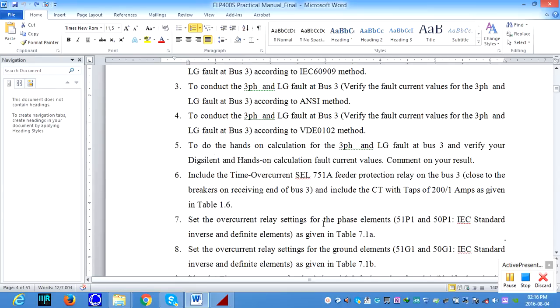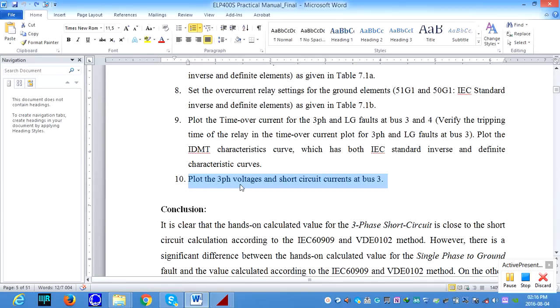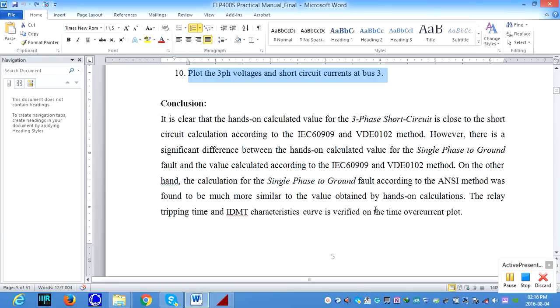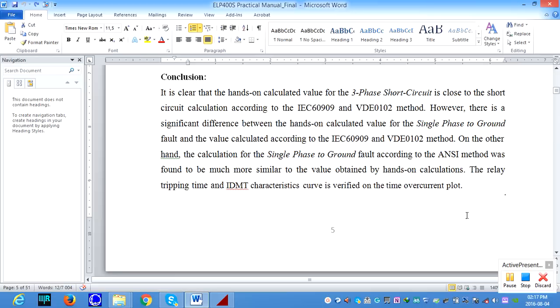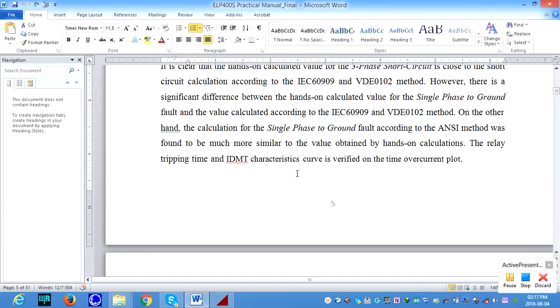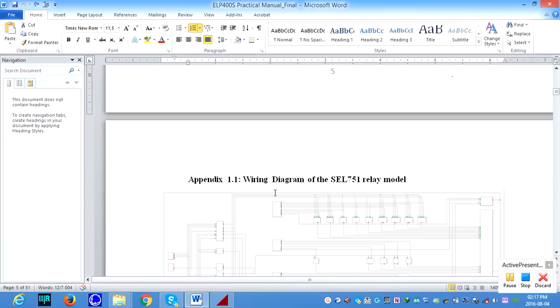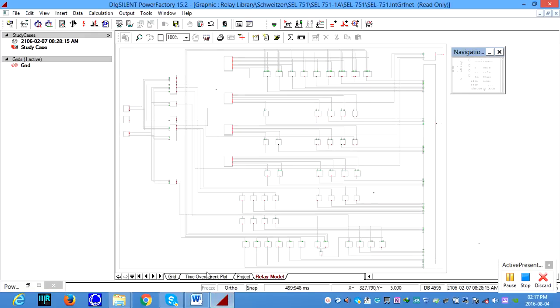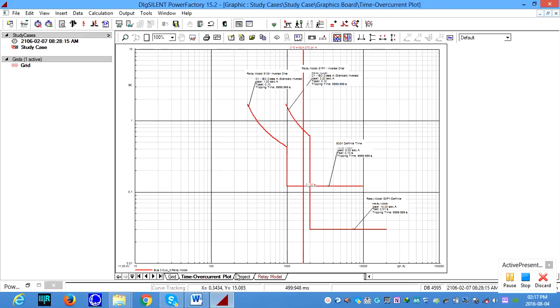Okay. So according to this description, the last step is this one, and the conclusion is that we applied a three-phase fault at different locations using different methods, the IEC and VDE methods, and we also did the hand calculation for single-phase-to-ground fault and three-phase fault. We compared the DigSILENT results with the hand calculation, and we also familiarized ourselves with the protection settings for this relay. We validated the tripping time of the inverse and definite characteristics, that combination being the IDMT characteristic, in the time-overcurrent plot. So that gives a conclusion of this project.